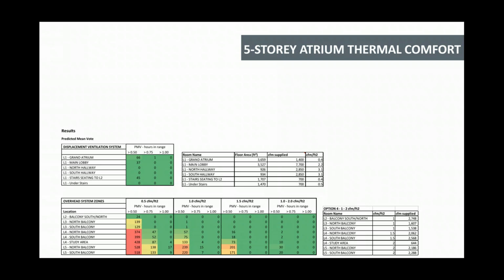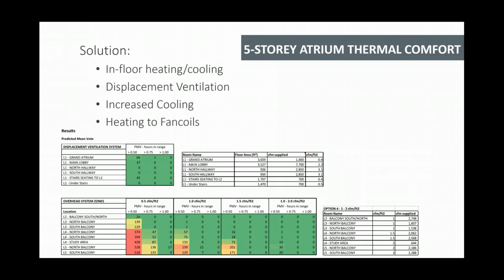Our thermal comfort model actually helped us design our fan coils around that atrium, in terms of how much ventilation we needed with the supply air temperature that we had. And you can see at the bottom of this page the different ranges that we had in terms of CFM per square foot out of those fan coils. In the end, we had a mixture where on levels 2 and 3, we had about 1 CFM a square foot. As we went up the building, we needed more cooling because of the stratification happening in that big atrium. Up at levels 4 and 5, we're at about 2 CFM a square foot for the design of the fan coils feeding the corridors on the outside of that open atrium space, just to maintain comfort for the students sitting around those corridor areas. So it was interesting that that drove the design.